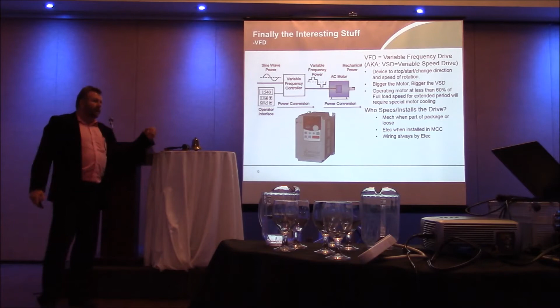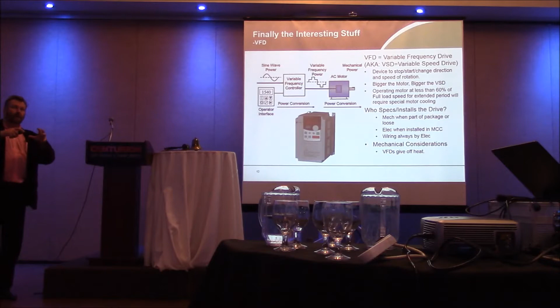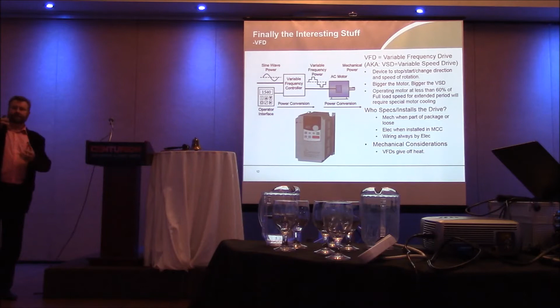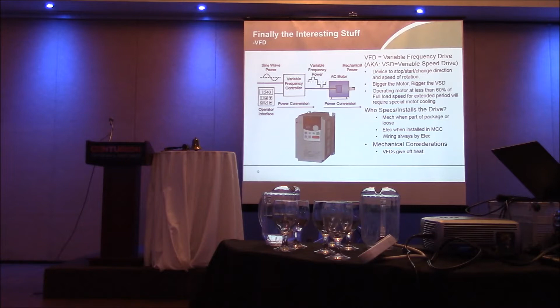Mechanical considerations. VFDs are not perfect. They give off heat, so they need to be ventilated. And the lower the speed you run them, proportional to the power output of the drive, the greater the inefficiency in the drive, the higher percentage of heat it will put out. So if it's a 100 horsepower motor and you're running the drive at 65 horsepower, per se, it's not going to be very efficient. It will put out a lot of heat. It will put out a higher percentage of heat at that level. When it gets up to 100%, it's generally a little bit better. All right.